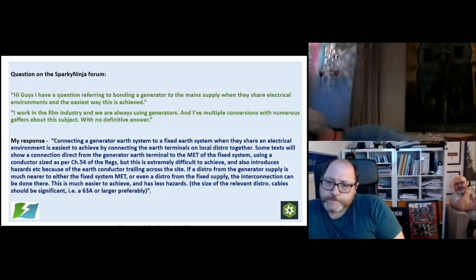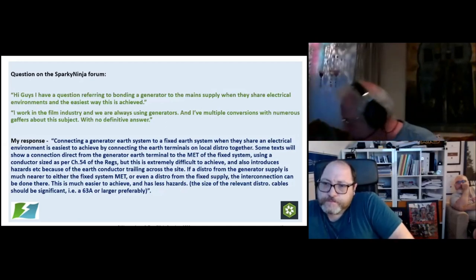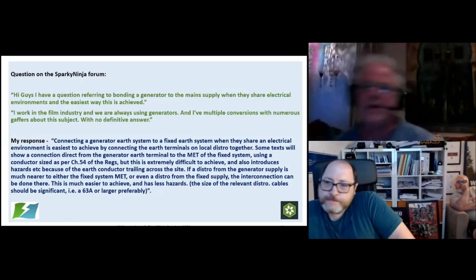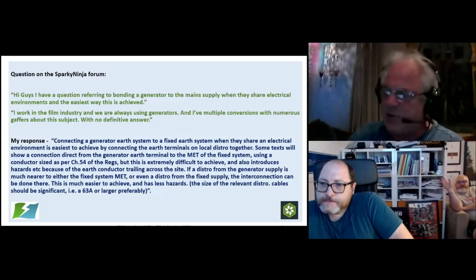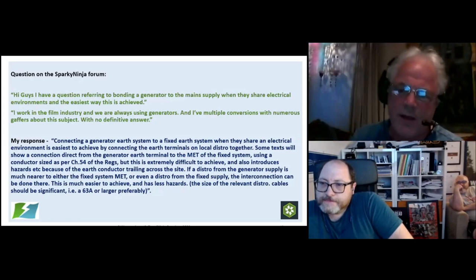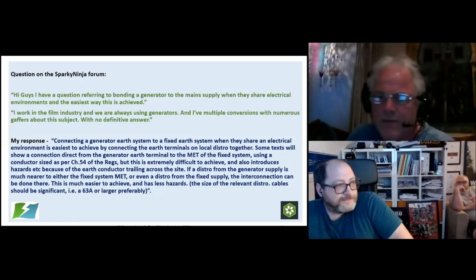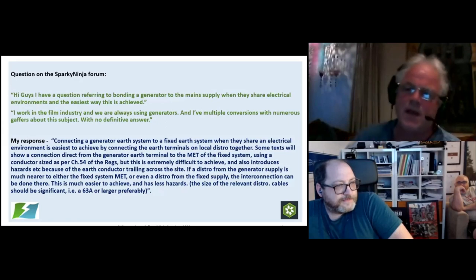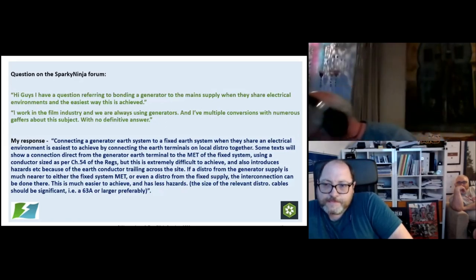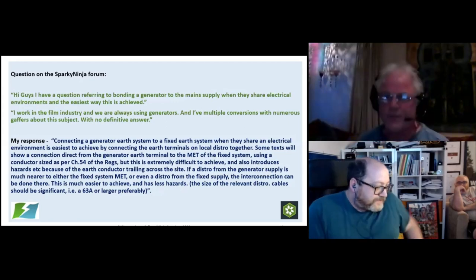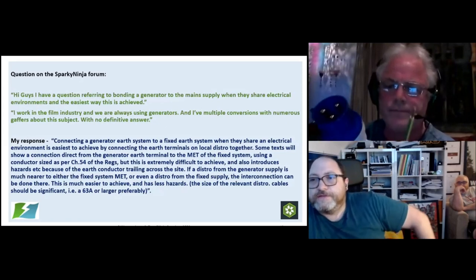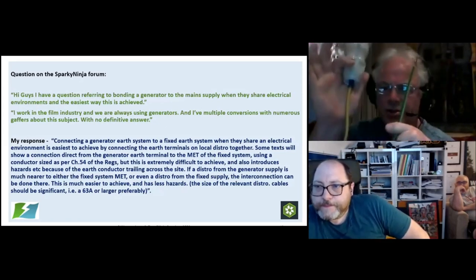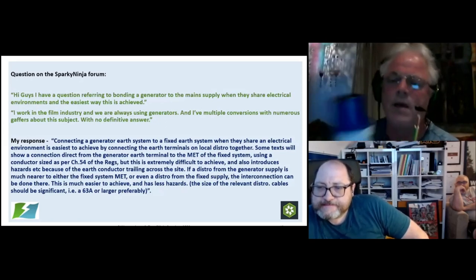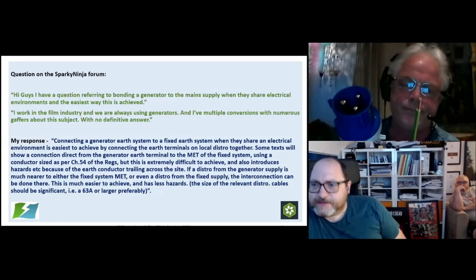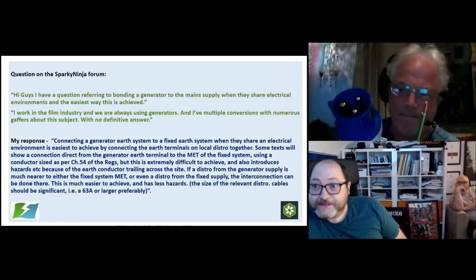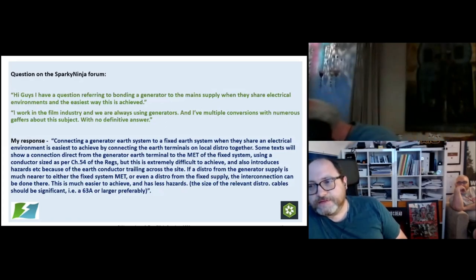Yeah, it is. And I'll show you what I've used before. Obviously, it means connecting onto an MET. If the MET is external to the fuse board, it's not so bad. If it's internal, then you've got to open the fuse board up, and you've got to look at the business of safety and everything else. So what we've had before is, and I've actually got them here, these. So that goes onto the MET. It's just a lead. That goes onto the MET, and that dangles off the DB. Okay. Then we have another lead.